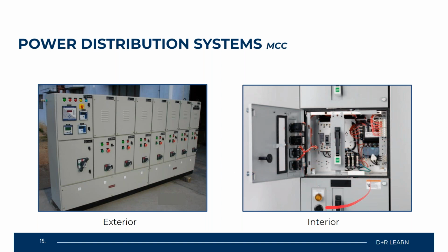Over to the right here, on the interior of your MCC panel, will be the electrical components that are used to power your motor system, such as fuses or any type of magnetic line starters you'll have associated with your MCC or motor control center. That way you have the ability to provide electrical power to your motor systems. Just want to throw one more thing in there: VFDs are other types of systems that can be associated with your MCC for power or control of the actual motor system. So you can do a combination of different systems when dealing with your MCC panel.